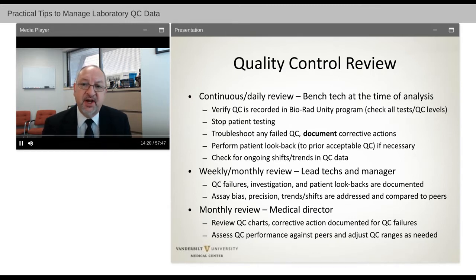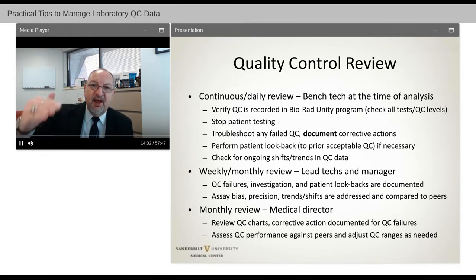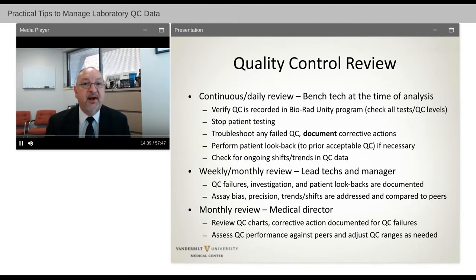We also want to check for shifts and trends. In other words, has our quality control data shifted very close to the 2SD or 3SD limits, whichever rule your laboratory is using, and is just hovering there, which may indicate that there's been some change in performance since we initially set up those target ranges.